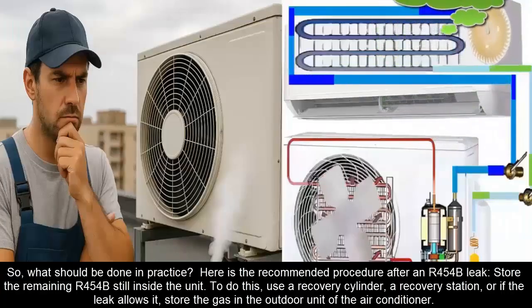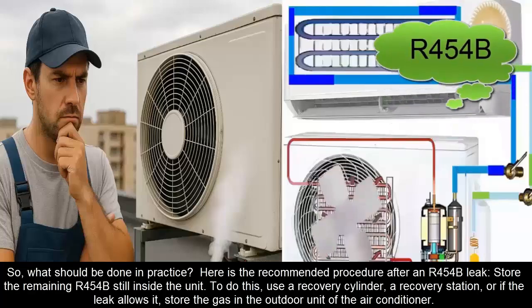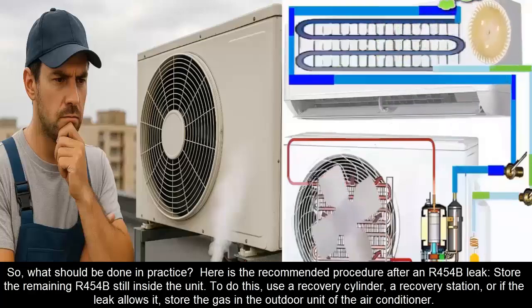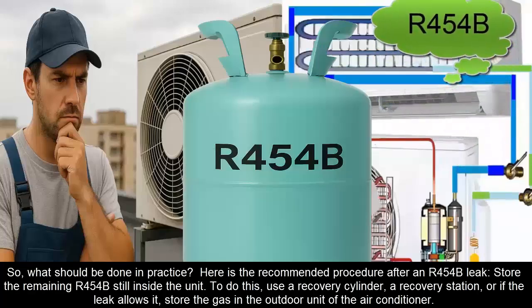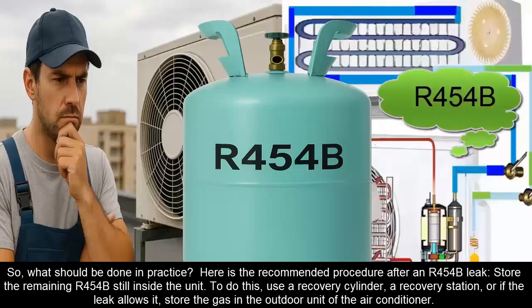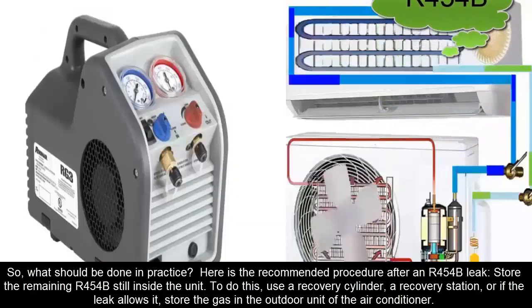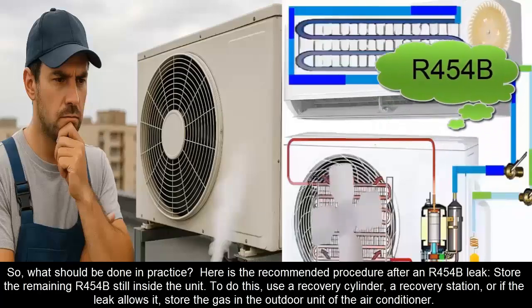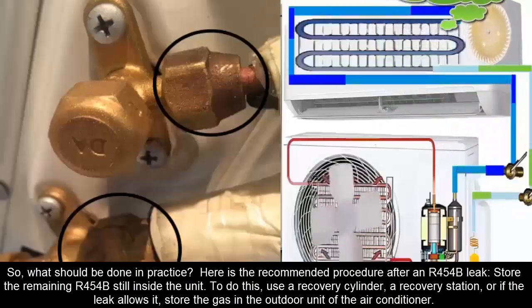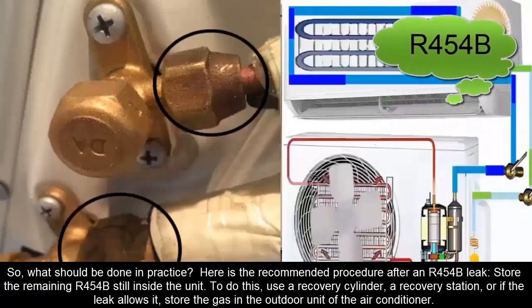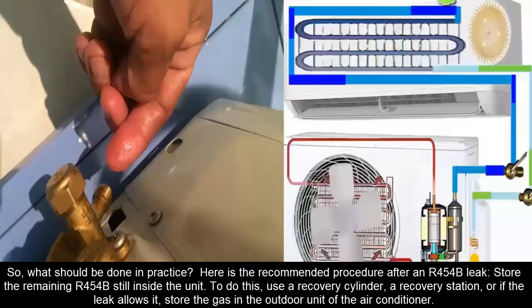So what should be done in practice? Here is the recommended procedure after an R454B leak. Store the remaining R454B still inside the unit. To do this, use a recovery cylinder, a recovery station, or if the leak allows it, store the gas in the outdoor unit of the air conditioner.